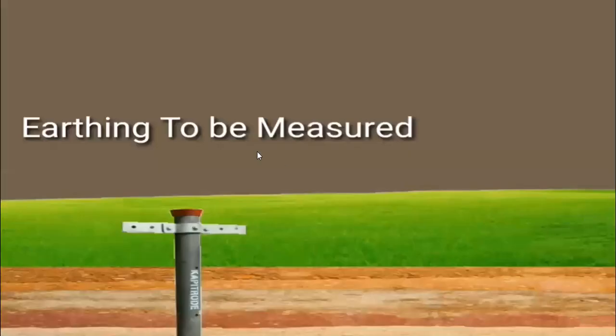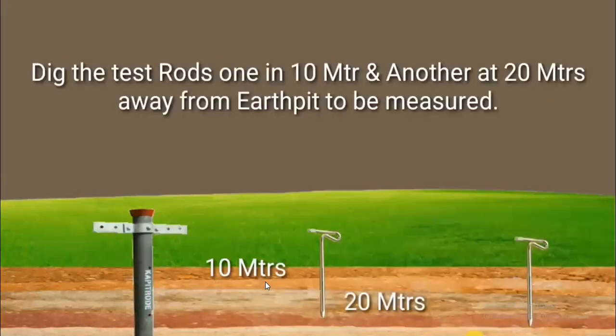Then next, the earthing to be measured. For this earth pit, we are measuring the earth resistance values. First of all, we have to place 2 test rods at equal distances. From the earthing pit, the first electrode or test rod is placed at 10 meters. Then the second electrode or test rod is placed at 20 meters from the earth pit. It is not necessary to place both rods in a straight line. We can place them anywhere, but you have to maintain the distance between the electrodes at the same value. That means maintaining 10 meters, and between the second and third, maintaining 20 meters.